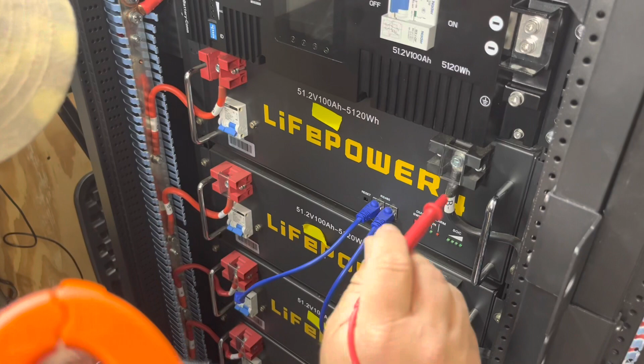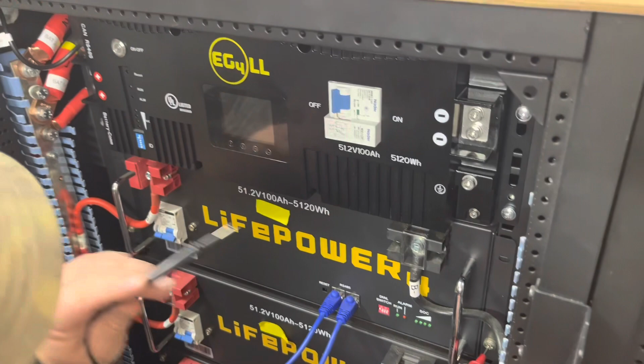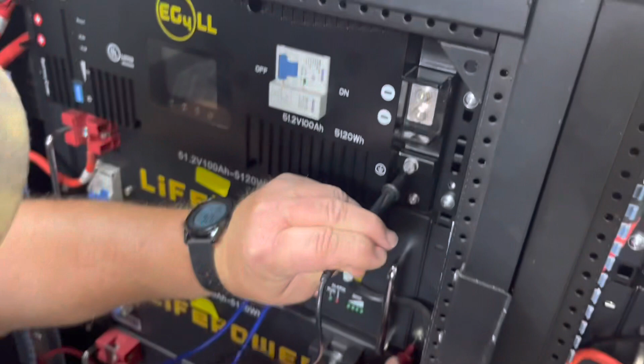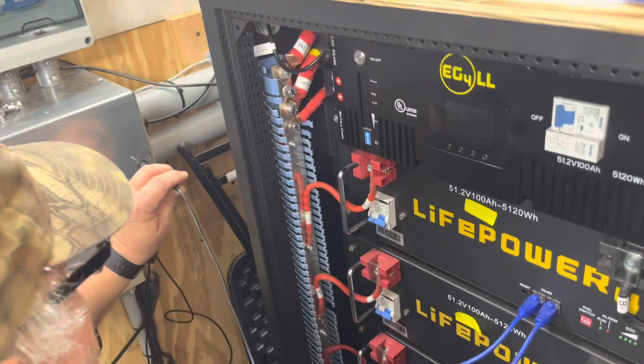All right, as I mentioned before, the older LifePower 4 batteries did not have a ground lug, and we were having to bond the frame of the rack through these rack screws. And we do have the rack frame bonded up in there, up under here. But I wanted to show you that this does have continuity. This is a rack screw here, and this is the ground lug there. So we are connected through the frame to the battery steel and to the ground. And also over here to our metal cabinet, or metal trough.